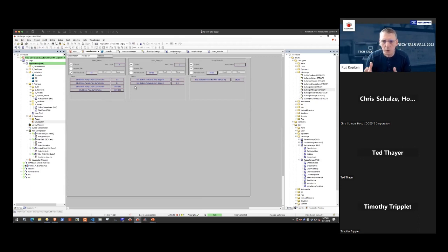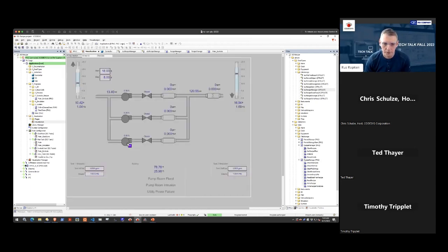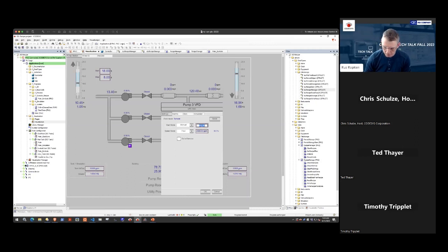And in this window, I hope you guys can see that okay on the other side. It may not be terribly big, but there's 3 different types of recipes here that have different settings. The first one I call the flow report. This one is periodically writing to the recipe, and right now I have it set to 60 seconds. So once a minute, it reads these values and writes them out to that recipe file. And that's really its only job. Read some values, write out to that text file. Let's start our pump back up so we get some good numbers going here.